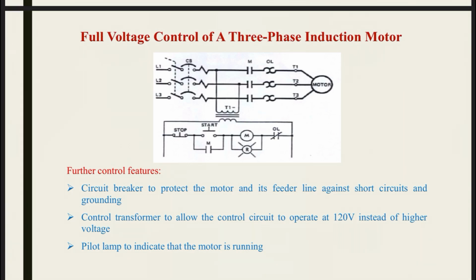Further control features here: a circuit breaker to protect the motor and its feeder line against short circuits and grounding. This is CB, the circuit breaker. Its function is to protect the motor and its feeder line against short circuit and grounding. We also need a control transformer to allow the control circuit to operate at 120 volts instead of the higher voltage, 208. This is the transformer T, a step-down transformer that steps down the high voltage.